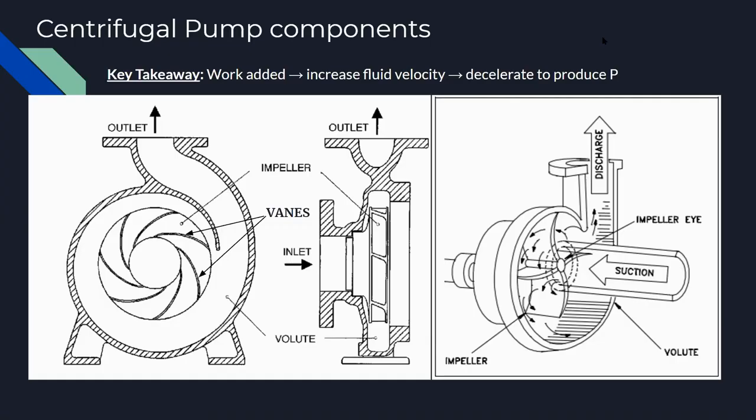Centrifugal pumps consist of three main parts: the impeller, the vanes, and the volute casing. The main point of these pumps is that the impeller does work on the fluid to increase its velocity, and then the casing trades this velocity for pressure.